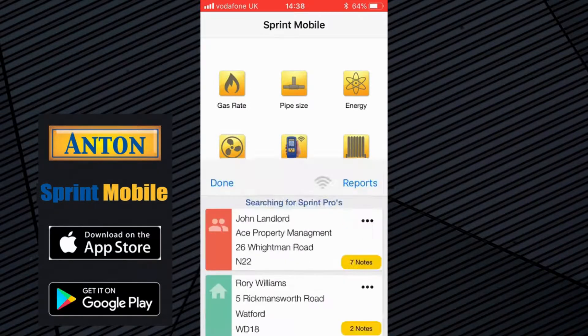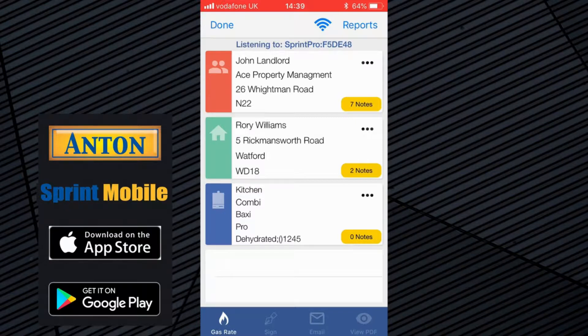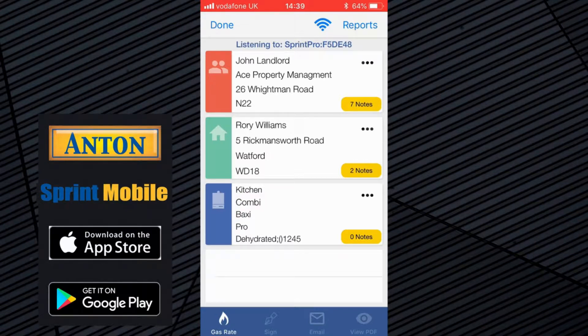So first thing you need to do is click on the Customers tab in the middle. I've already created some reports here — some flue gas reports for this customer. Obviously you would normally need to do that: you take your flue integrity test. I'm talking about a high efficiency boiler here, so a low fire and a high fire. But you can also add let-by and tightness test if you've done one with your analyser, so you can incorporate that — operating working pressure, gas rate.